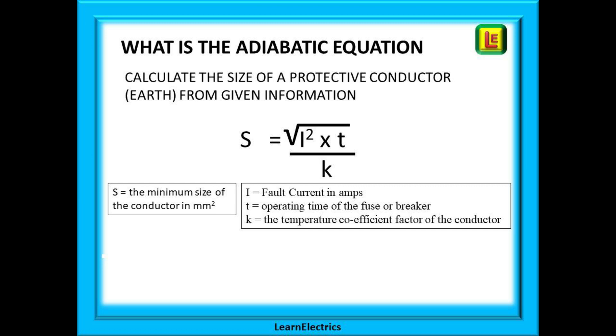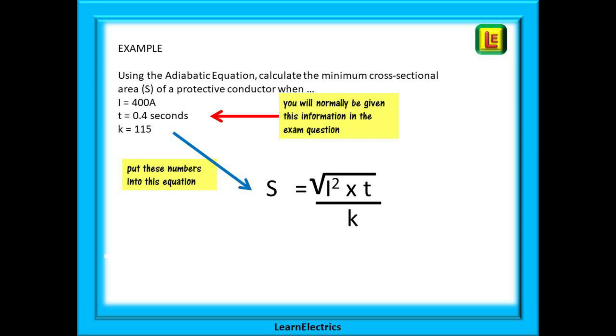So why not do an example of this? Here is a typical exam question. Using the adiabatic equation calculate the minimum cross sectional area or S of a protective conductor when I equals 400 amps, T equals 0.4 seconds and K equals 115.